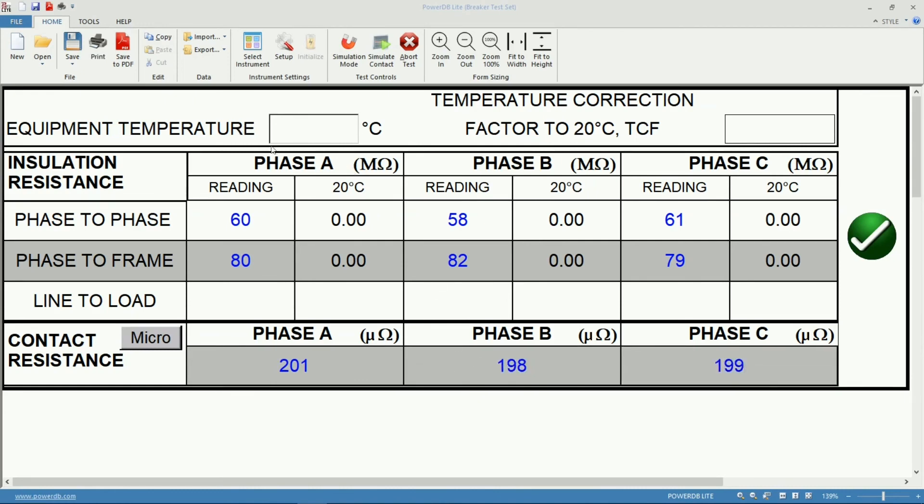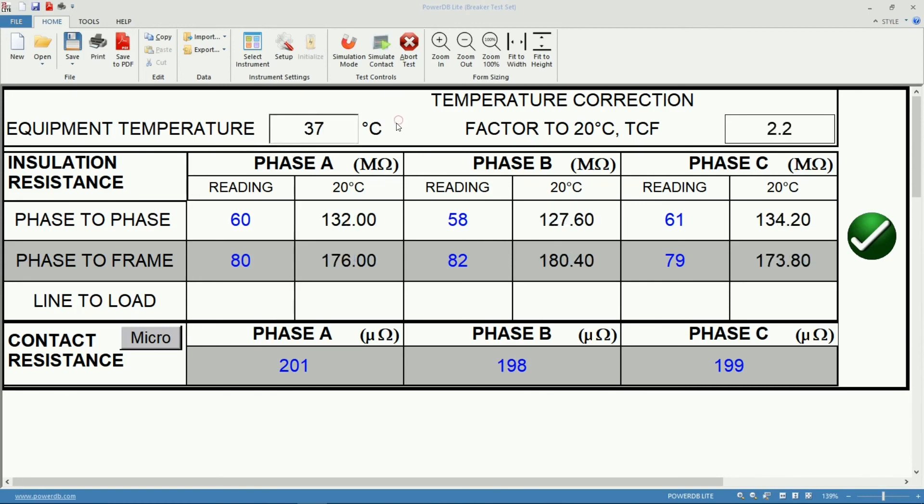Also notice that right now my equipment temperature is empty. We measure our temperature and let's say it was at 37 degrees celsius. As soon as I accept that value the software will actually correct my insulation resistance measurements back to 20 degrees celsius so I can compare with previous readings.